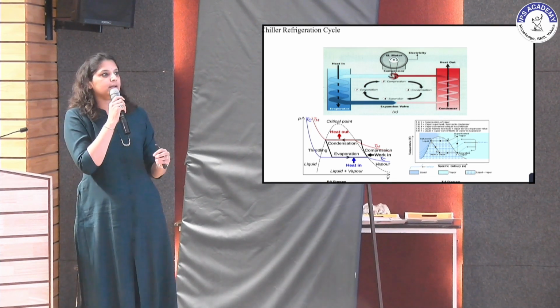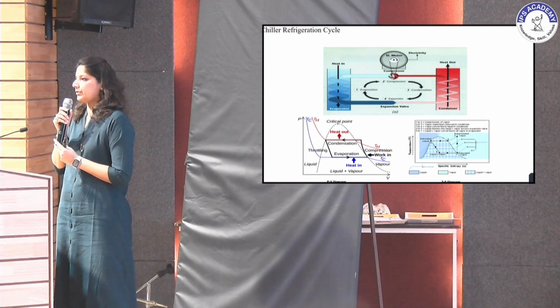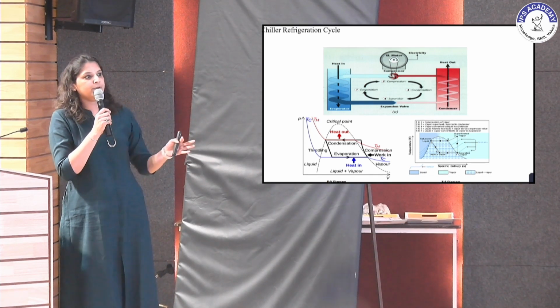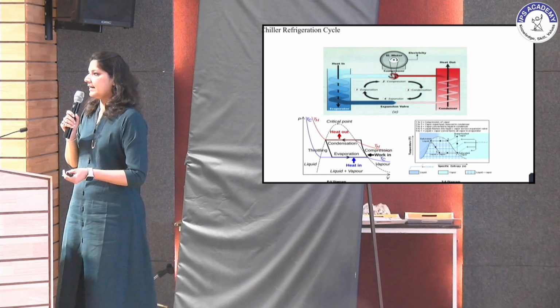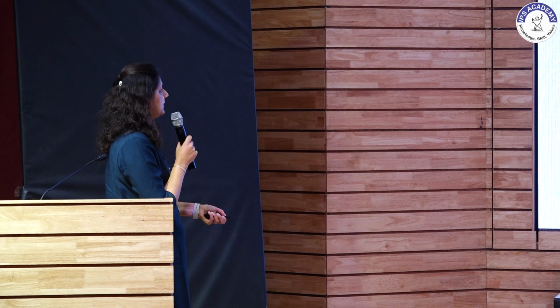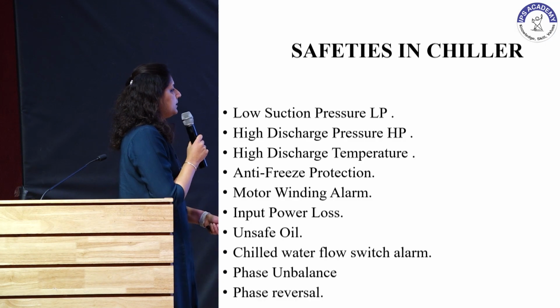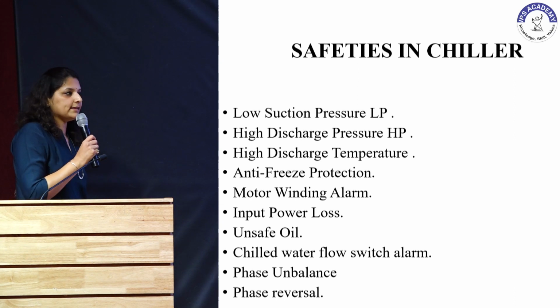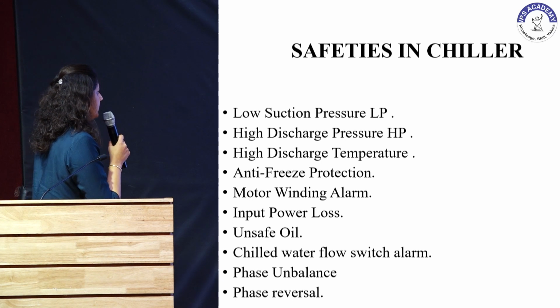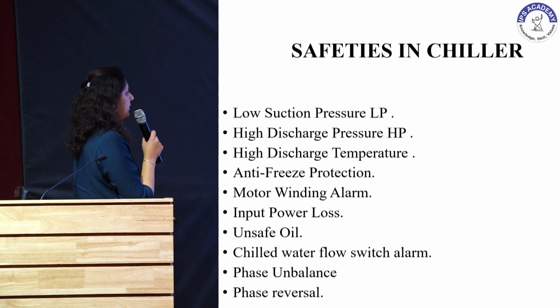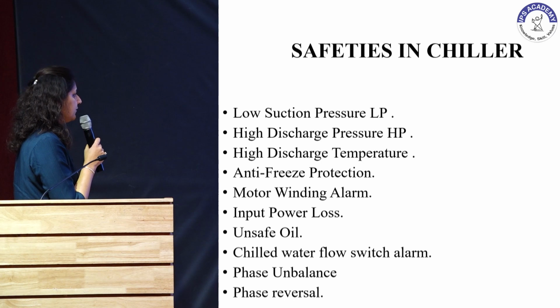We have to keep in mind that we should not have only one approach while we are putting the chillers to service. We have to have the maximum 360-degree approach and see whether it is the evaporator, condenser, expansion valve, or even a filter dryer that can be choked and is causing major trouble to the chilling cycle. We have covered most of these things. So these are the major safeties which you have to observe while servicing a chiller: low suction, high discharge pressure, high discharge temperature, antifreeze, motor winding alarm, input power loss, unsafe oil, chilled water flow switch alarm, phase unbalance or phase reversal.